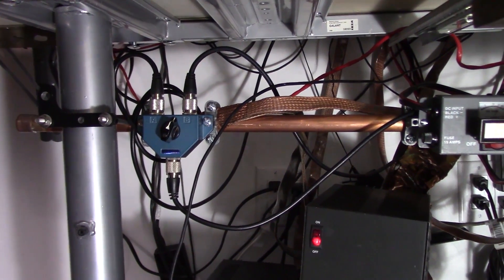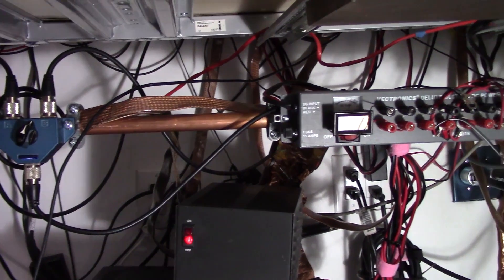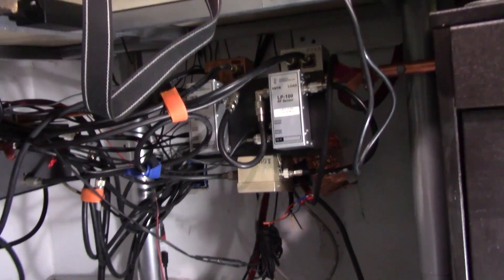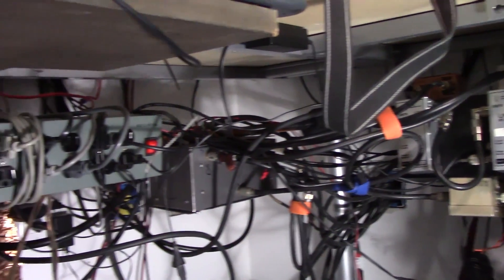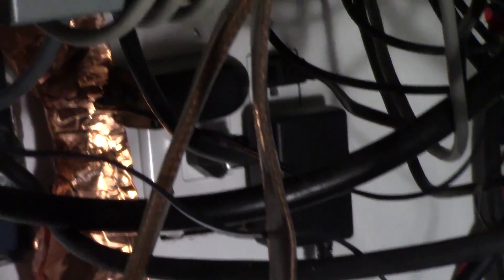On three walls there are two strips of copper. This copper runs around the room, one on top of the other, so I have about six inches of this stuff. It comes out of the wall and connects to a copper pipe underneath the desk — a three-quarter inch copper pipe. Here's the underside of my desk. There's the copper pipe that runs under the desk to the three legs of the L-shaped desk. That copper pipe is in turn connected to grounding straps — there's one that leads to a one-inch copper pipe. Each piece of equipment is then connected; the braid is attached mechanically to the pipe with a clamp.